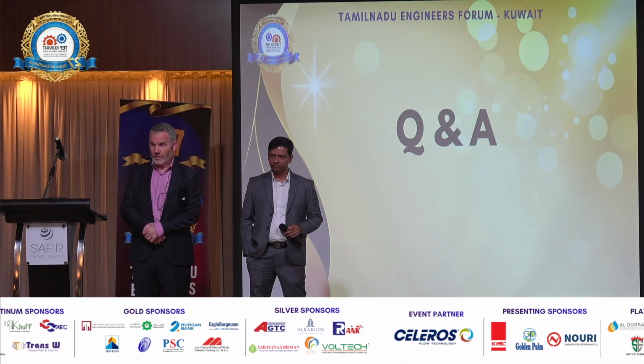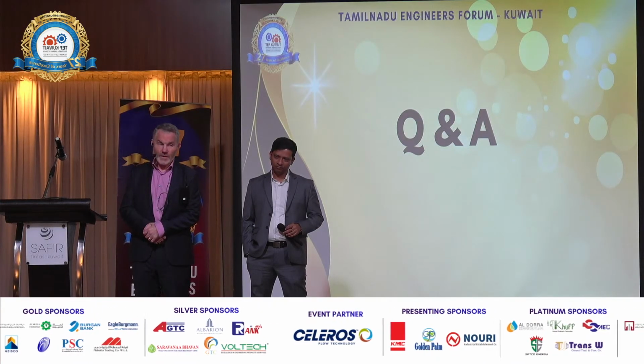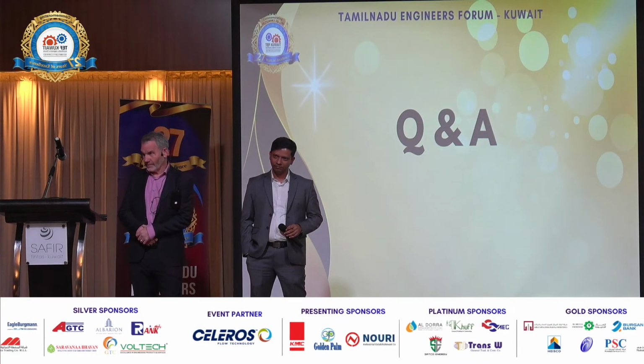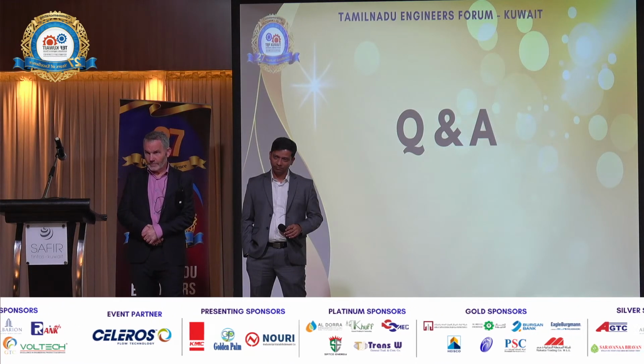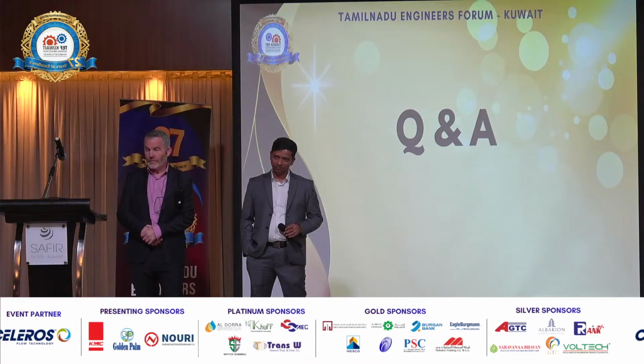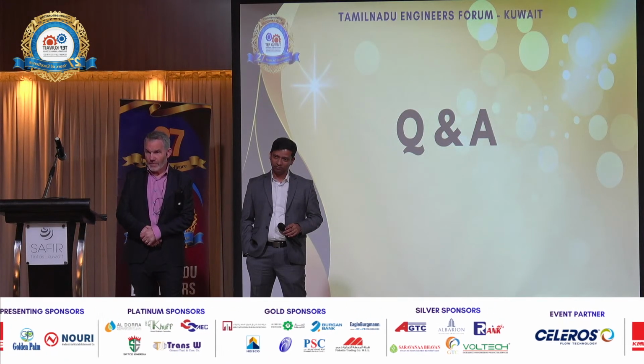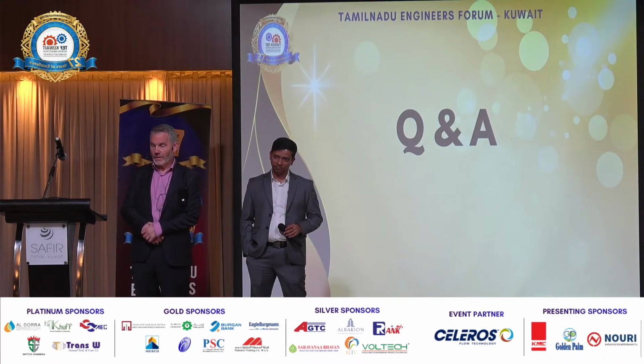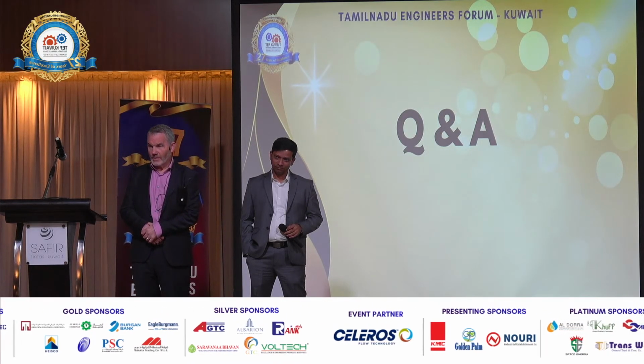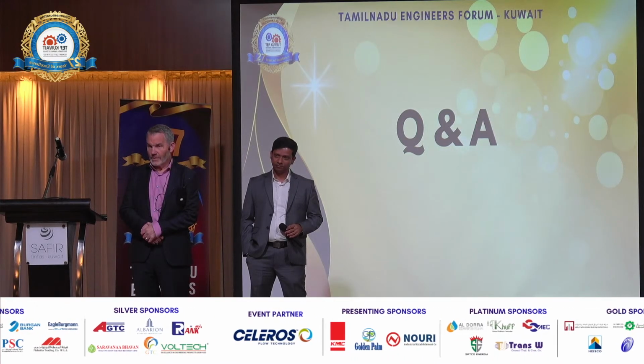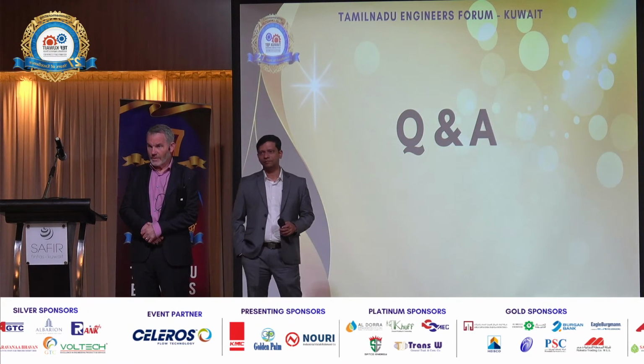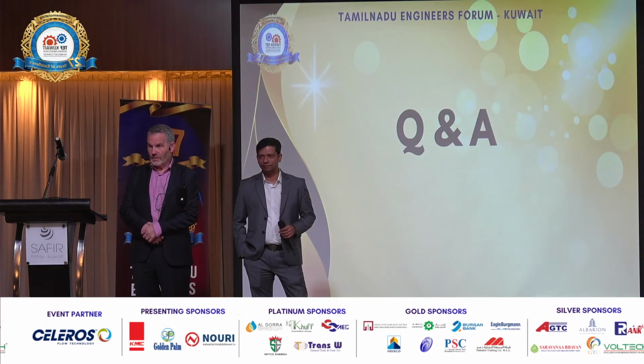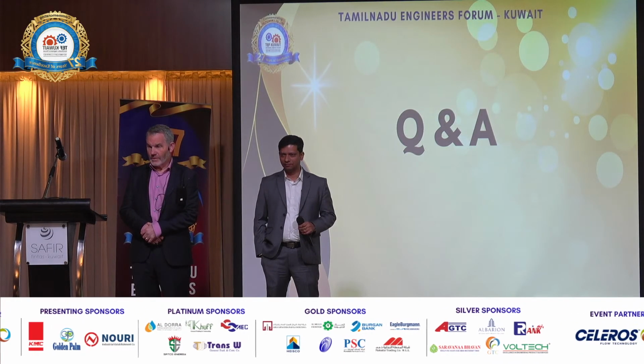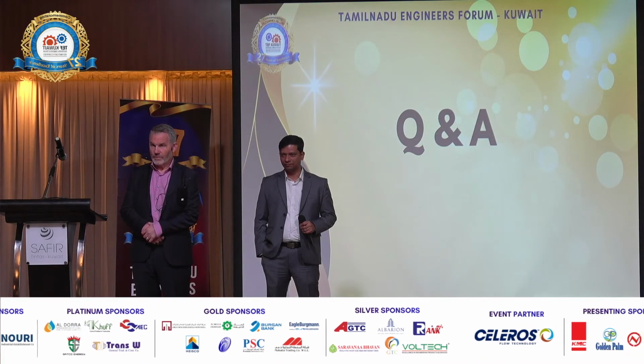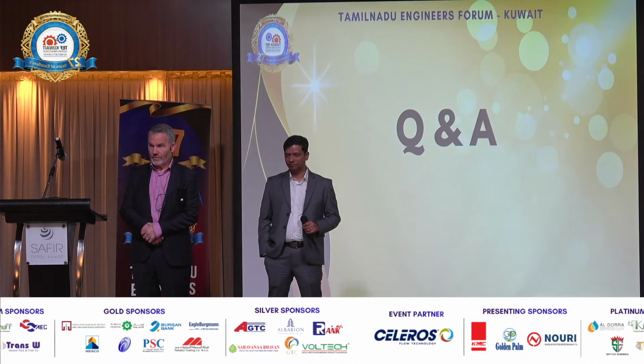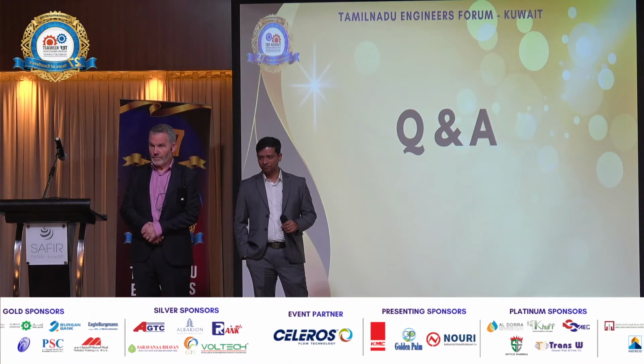Okay, I will go to the next question. We are talking about the BEP, best efficiency point. As per the standard, API 610, you need to maintain 80 to 120% of BEP. Due to sizing and costing, economic reasons, so many pump manufacturers are giving 50 to 60% of the BEP. That means just away from the BEP point. Is it recommendable or acceptable from a working point of view? I'm asking.